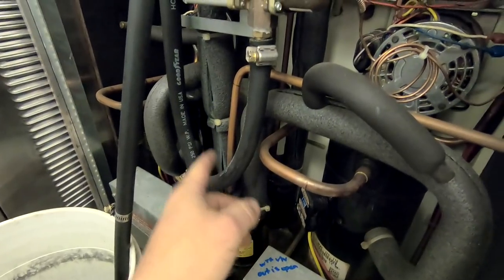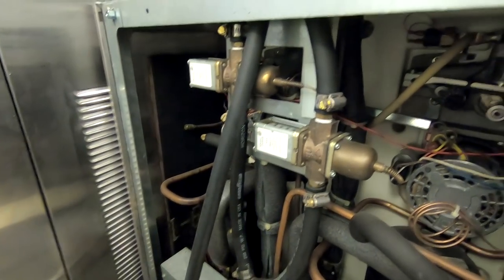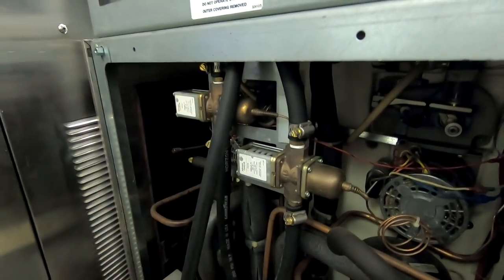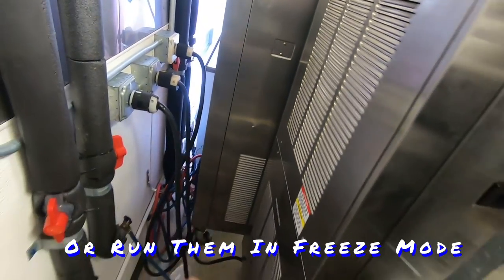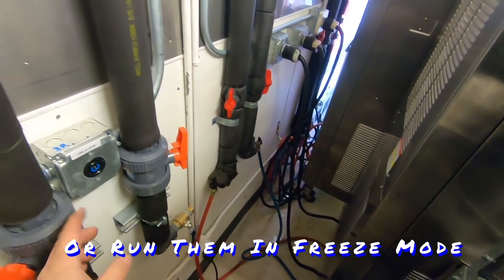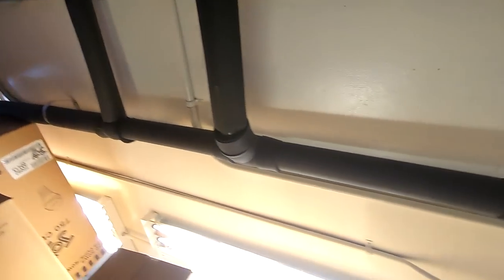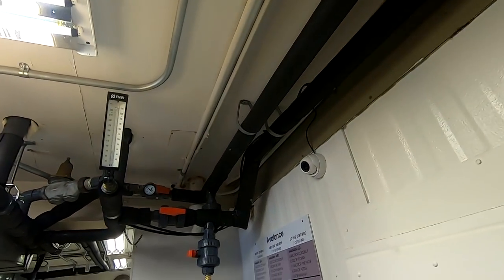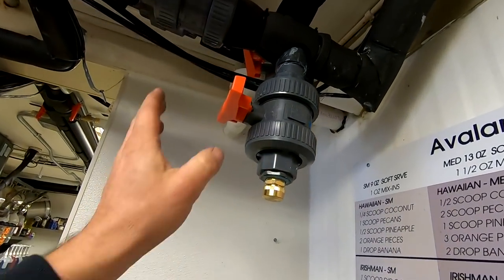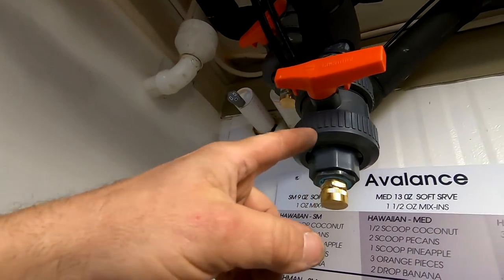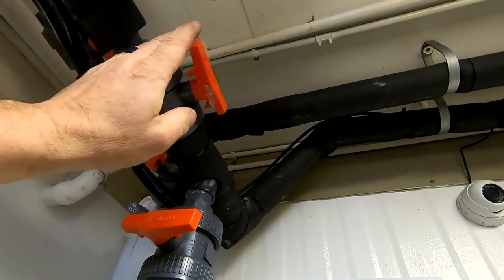And to bleed the machine is going to be the same scenario. We're going to leave these backed out and then I have to do that but also these other two machines that were existing. And we can actually isolate these things one at a time. They come up here to the top, come across and what we did is we've got valves about here and here so that we can loop our pump down and back again.